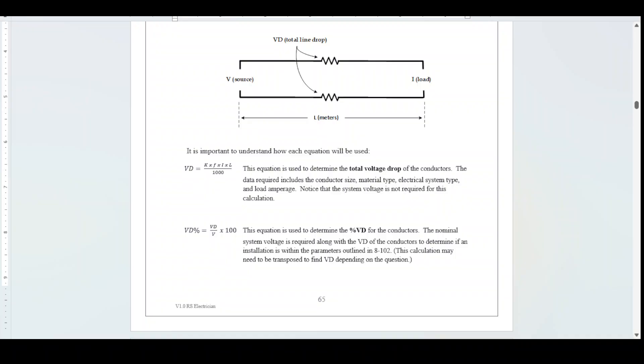The percent V_D equation is used to determine the percent voltage drop for the conductors. The nominal system voltage is required along with the V_D of the conductors to determine if an installation is within the parameters outlined in rule 8-102. This calculation may need to be transposed to find V_D, depending on the question.